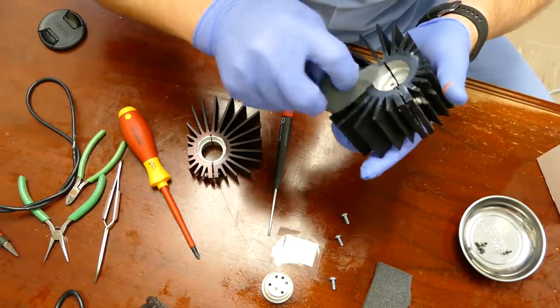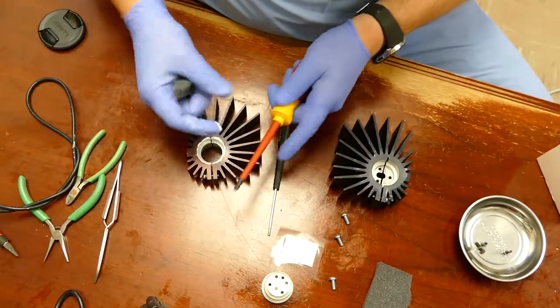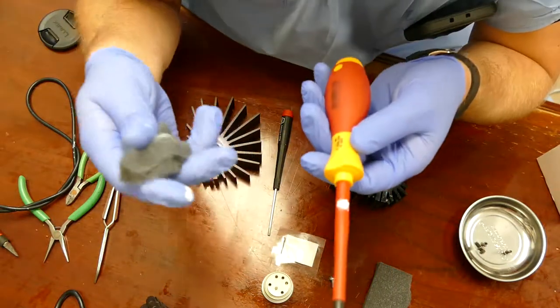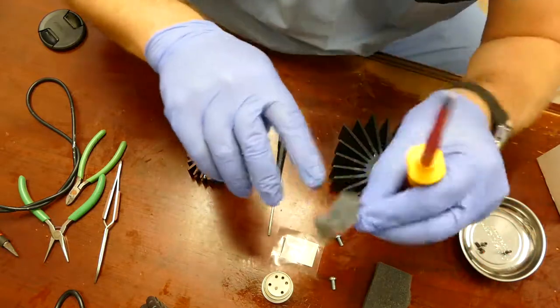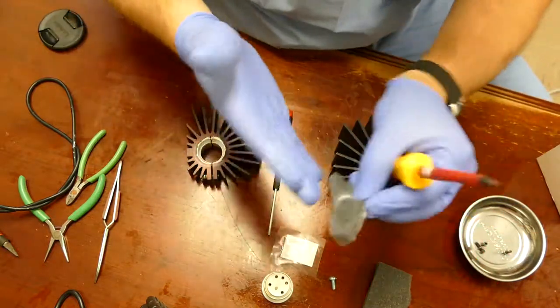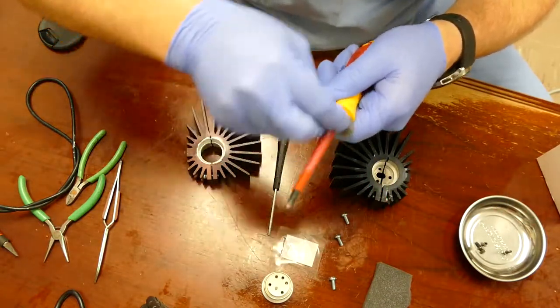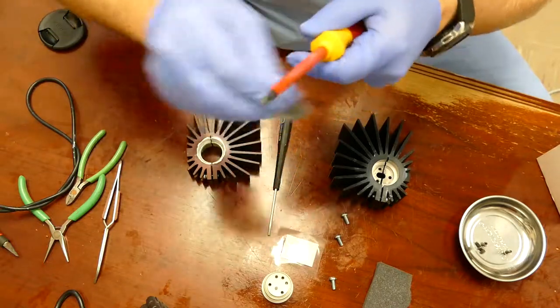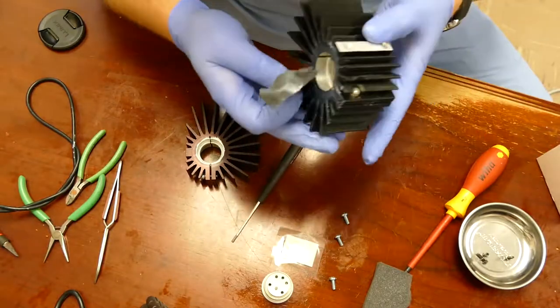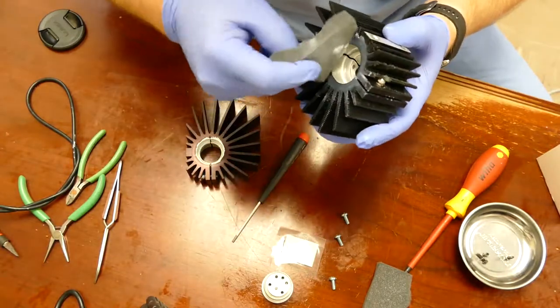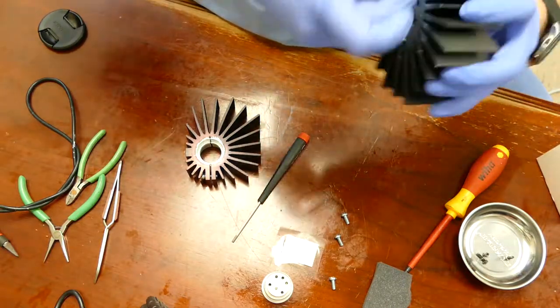Don't leave it on your desktop. When this white garbage gets on something, it makes an absolute mess, so try and maintain as little bit of a mess and a clean work environment, because you don't want to get the stuff on the face of that bulb. These bulbs are about $220, so try and be nice to it. If you happen to get some of the white goo on some of your tools or even on your gloves, you don't have to change out your gloves. Just take the foam and rub it on your glove, and it's like a magnet for this white goo. See that? Cleans it right up, keeps it on the foam.